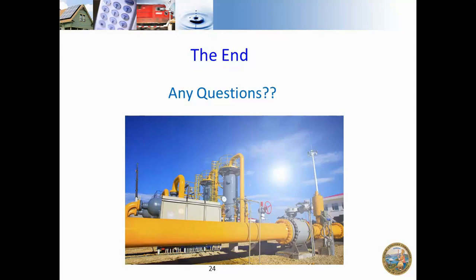The design formula for steel pipe is in 192.105, and for plastic pipe it's 192.121. If you don't have prior pressure records, you can utilize that design formula under 192.619 to determine what your maximum operating pressure is — so you can figure out if you are going above and beyond that limit.